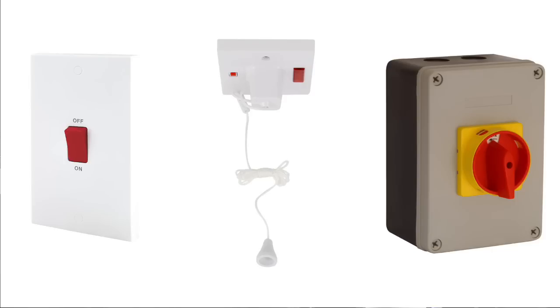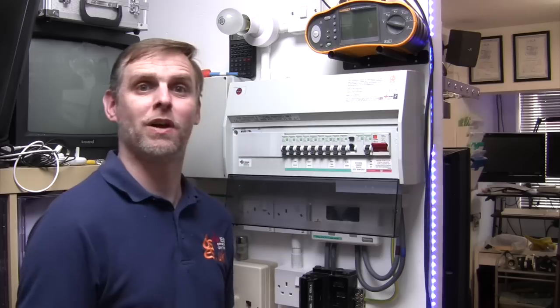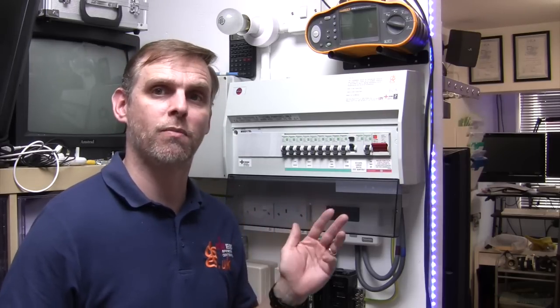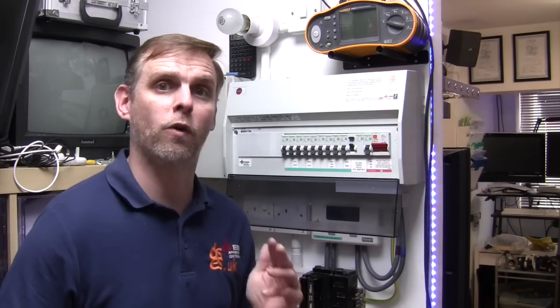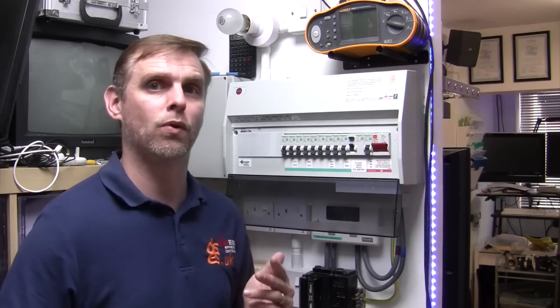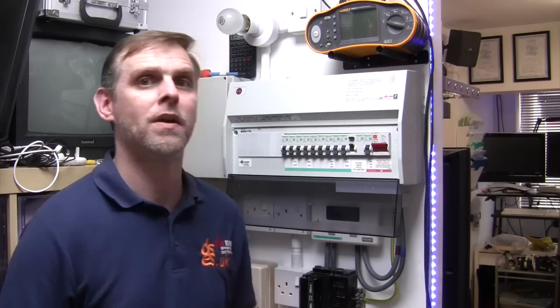These types of isolator may be located at the physical location where you're working, in which case locking them off is perhaps not so important, as it's not so easy for the supply to be re-energised by someone else without you noticing. But if the source of supply is remote, or others are also working or present on the same site, it's important the source of supply is locked off so it cannot be re-energised without your specific knowledge and intervention.